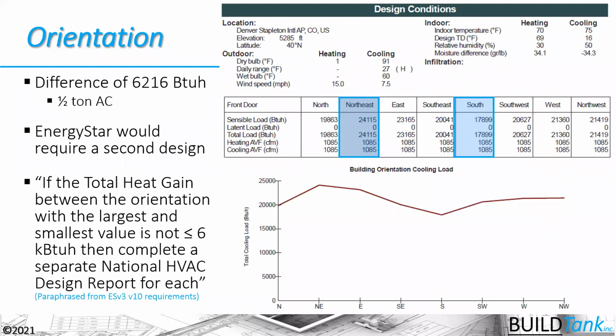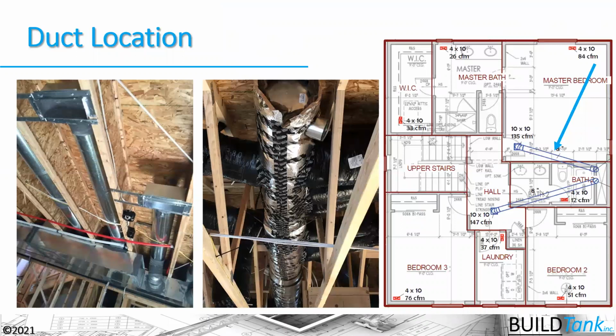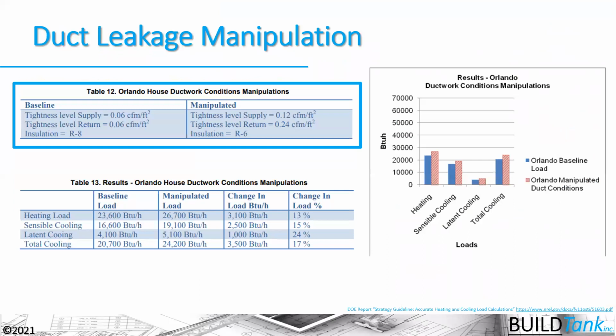Now, Energy Star says that any orientation that is more than 6,000 BTUs different has to get its own HVAC design. But again, the code doesn't require that, but it is something that specific jurisdictions might consider looking at there. And it's something that you should look at in your HVAC review if you're a code official, for example. Duct location and duct leakage is another thing that can be looked at. The ducts inside the envelope or outside the envelope, how are they insulated? How tight are they? And what are their ultimate impacts on the ultimate sizing of these systems?